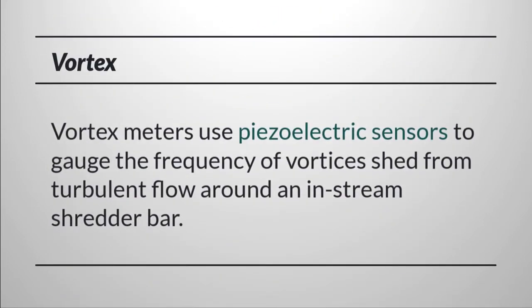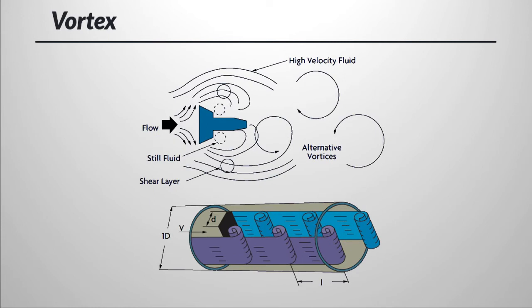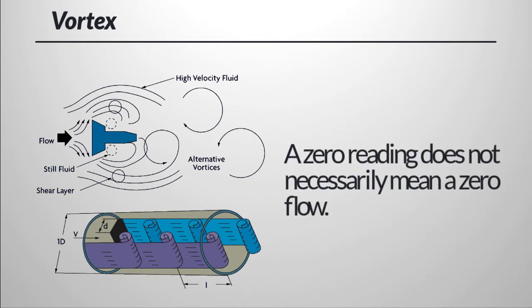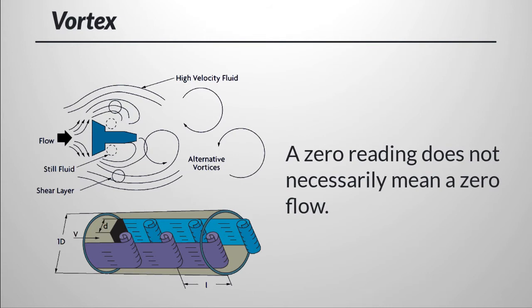Frequency-based technologies include vortex and turbine flow meters. Vortex meters use piezoelectric sensors to gauge the frequency of vortices shed from turbulent flow around an in-stream shedder bar. A piezoelectric sensor detects the pressure oscillation around the bar, or a piezoelectric strain gauge detects the forces exerted on the bar. The vortex shedding frequency is directly proportional to the velocity of the fluid in the pipe, and independent of fluid properties such as density, viscosity, and conductivity. The flow must be turbulent, so a zero reading on a vortex meter doesn't necessarily mean zero flow.